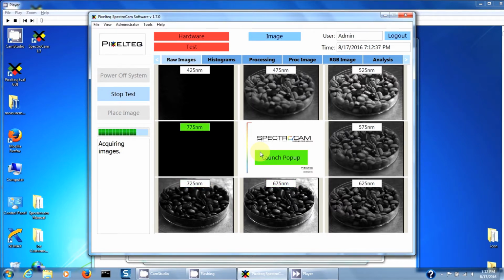This option allows the user to determine the amount of rotations the filter wheel will make during the measurement before it returns to its home position. In this example, we selected Continuously to show live updates. Remember, if you are saving data, the hard drive will store every image and storage space will quickly reduce.